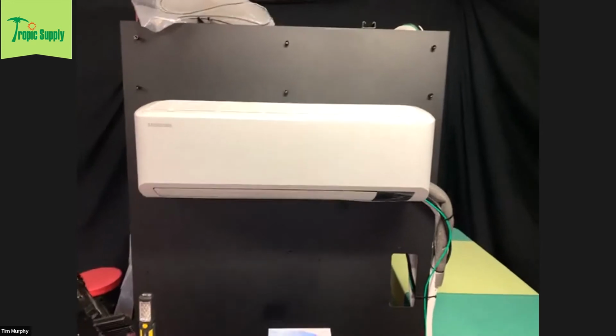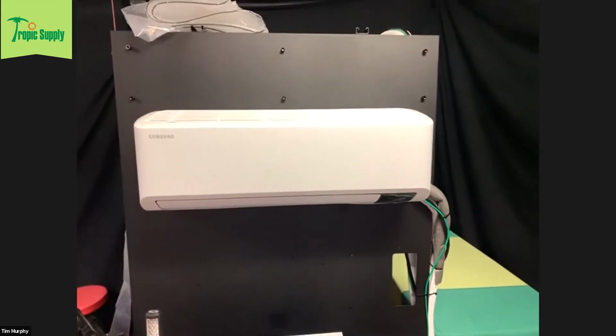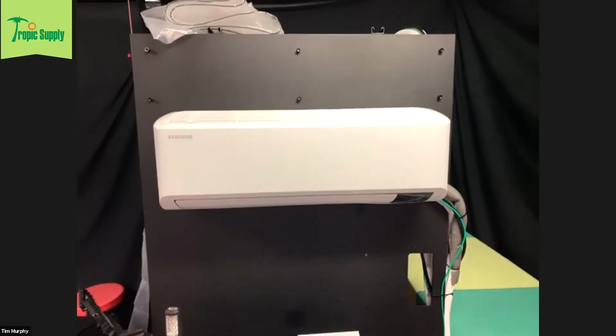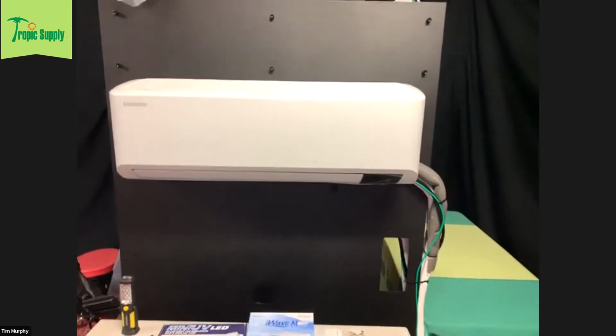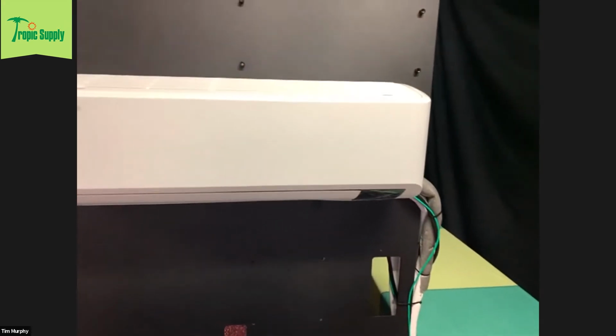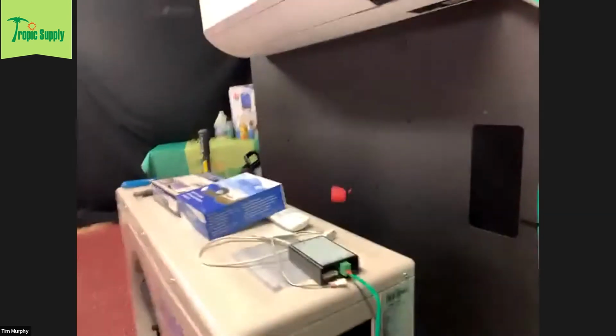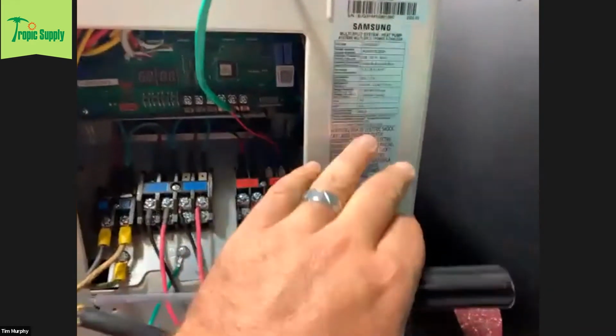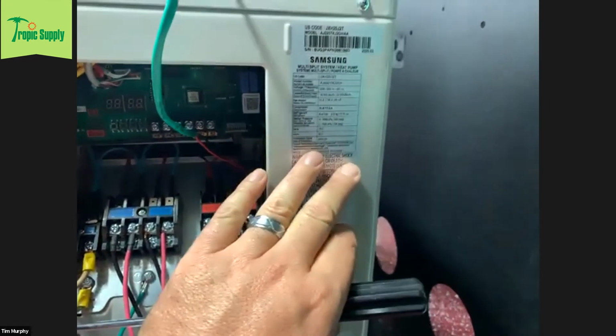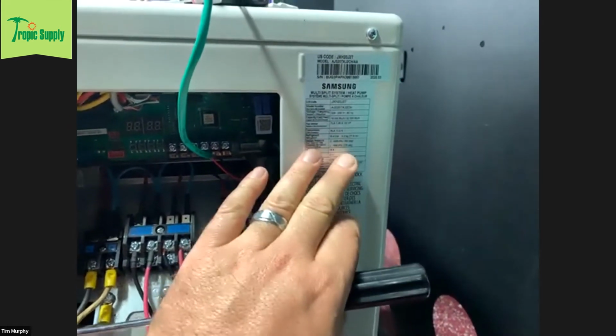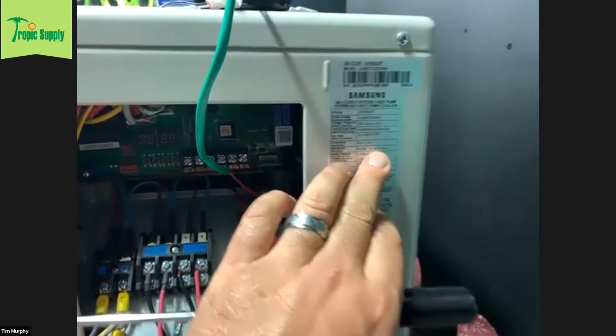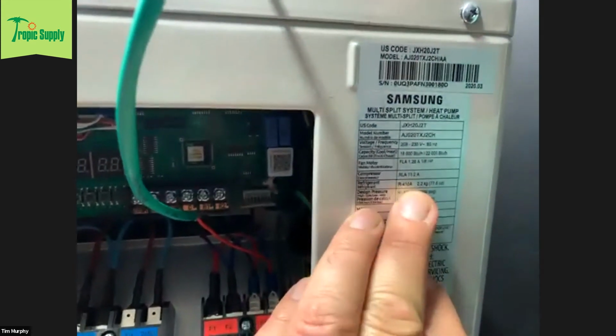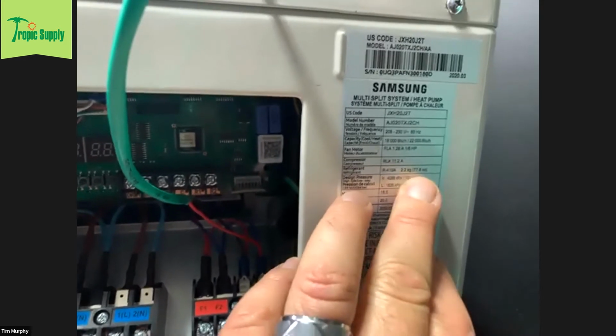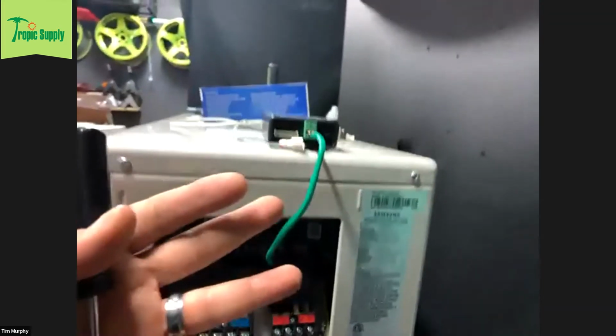So just get your reclaimer out and reclaim all the Freon. Most mini split systems I've ever worked on will show on the nameplate, on the side here, how much Freon to use. So if you pull all the Freon out, you'll see it says R410A, and it tells you the charge in kilograms and ounces so you can weigh the charge back in.